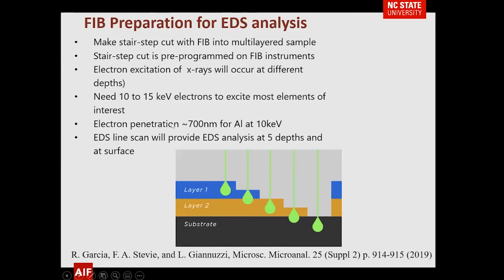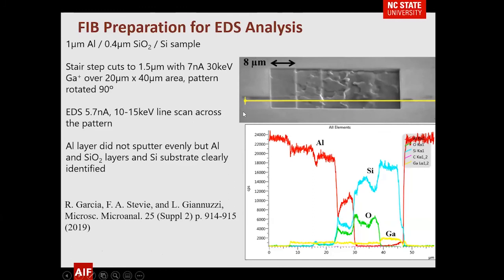One more example: preparation for energy-dispersive analysis designed for quick look. Here you can see the stair-step we used before. We do an EDS line scan at various locations going deeper into the material. We know electrons penetrate a certain distance, which prevents doing this directly with EDS because of signal coming from layers below. The FIB cut took less than five minutes. The EDS line scan shows you going through the aluminum layer, then picking up an SiO2 layer, then totally into the silicon. The gallium signal gives an idea of how much gallium resides in the material after analysis.